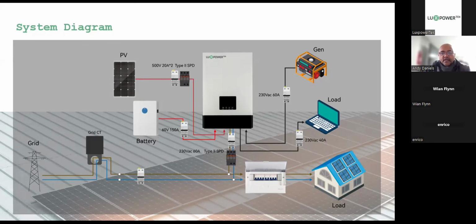And then from here, you have your loads going out, your essential load. Here you have your generator input. You'll see that the generator input breaker is also rated 60 amps. The load breaker on the 6 kilowatt on the EPS side is 40. And here we've got 60 amps going in.